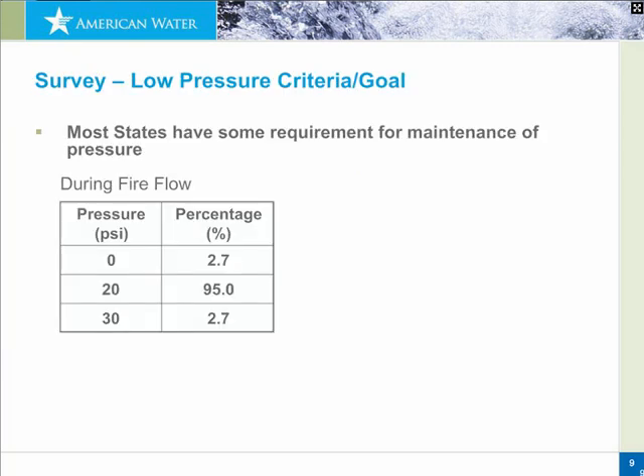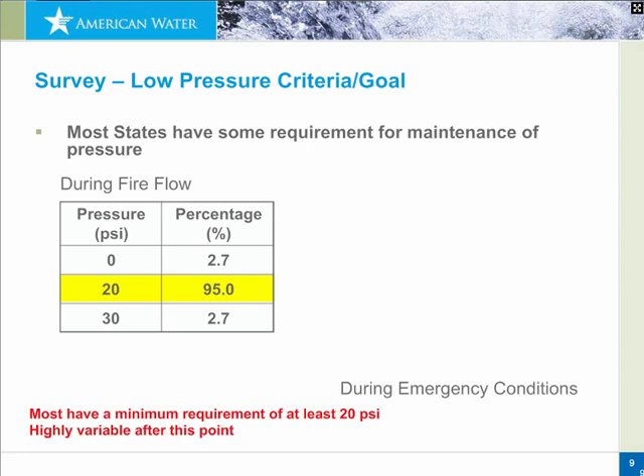We asked these utilities, do you have a goal or criteria for maintenance of pressure in distribution systems? Most systems — 95% — said yes, under fire flow we try to maintain 20 PSI, which reflects the 10-state standards for typical operating conditions. We then asked about emergency conditions, and about 68% said they try to maintain 20 PSI, and the remainder said they try to maintain at least positive pressure in the distribution system.